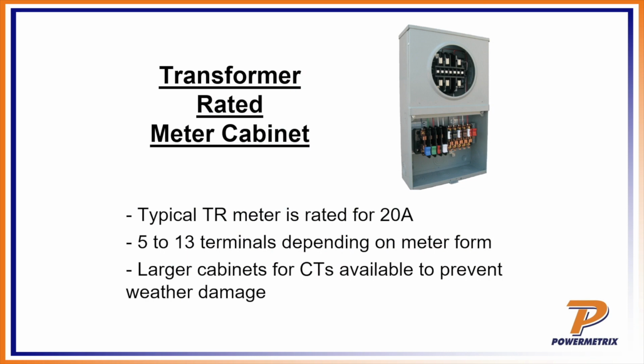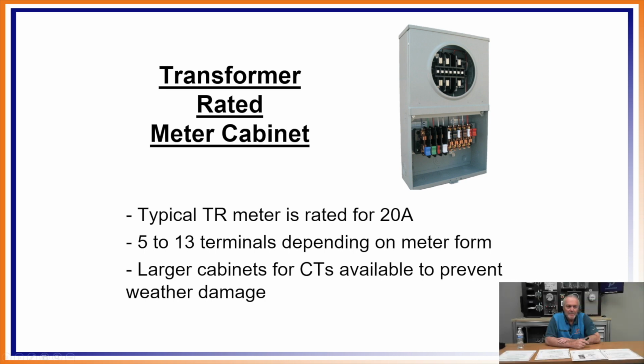Transformer rated meter cabinets. Here we've got our good old test switches in the bottom of it. You can see right below the meter there. They're rated for 20 amps. Now we're going all the way up to 13 terminals with the transformer rated. And then the larger cabinets for the CTs are available. So you can see where you open up, the CTs are actually within the cabinet as well. Okay, so that's what we're talking about on that last point.